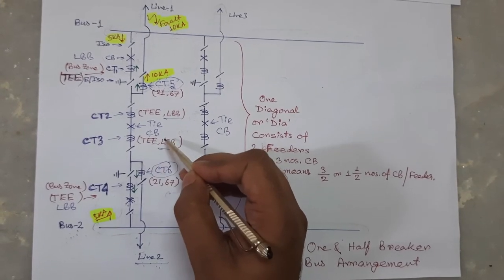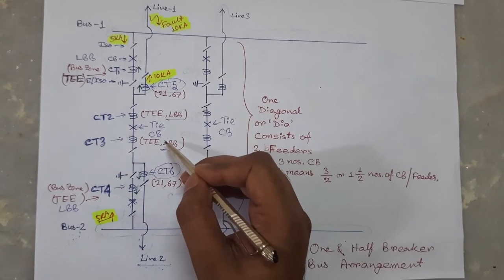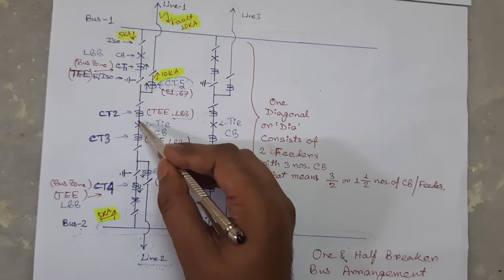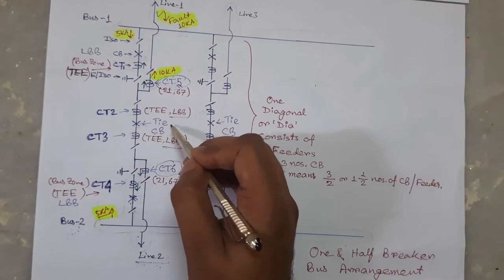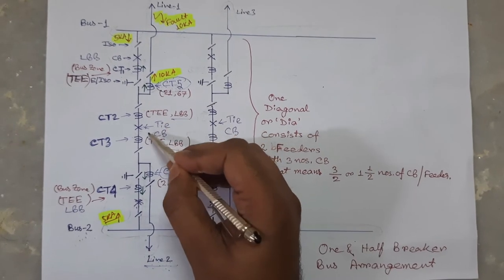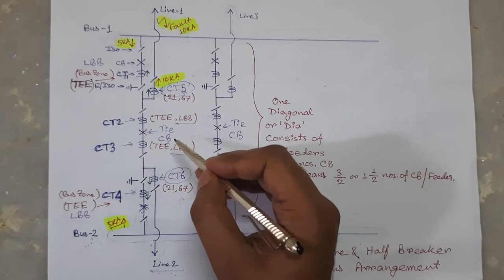And after initiation of tie LBB protection, it waits for a predefined time delay, say 200 millisecond, in a hope that this tie circuit breaker will be able to clear the fault.